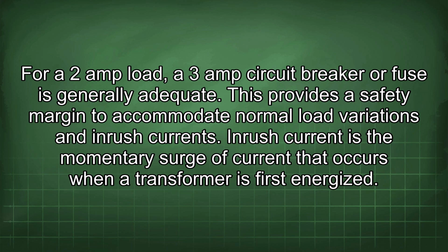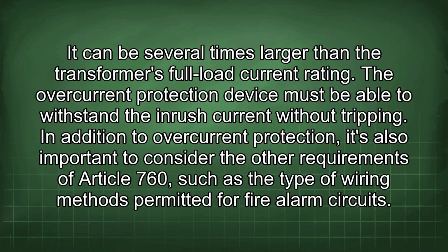Inrush current is the momentary surge of current that occurs when a transformer is first energized. It can be several times larger than the transformer's full load current rating. The overcurrent protection device must be able to withstand the inrush current without tripping. In addition to overcurrent protection, it's also important to consider the other requirements of Article 760, such as the type of wiring methods permitted for fire alarm circuits.